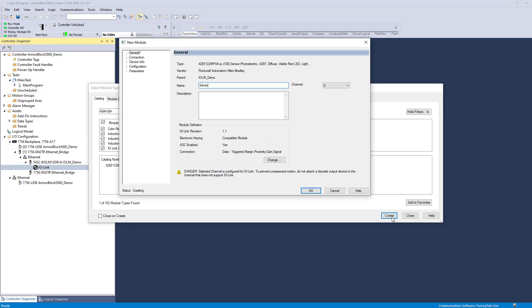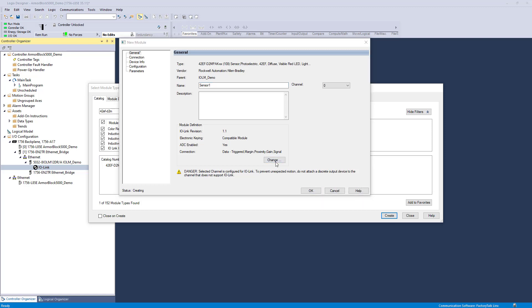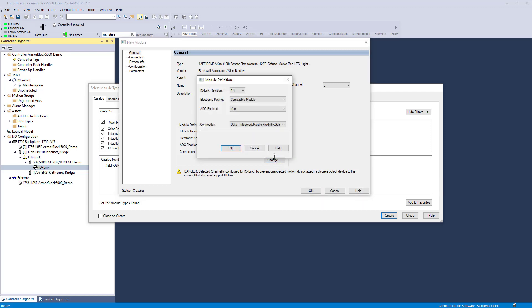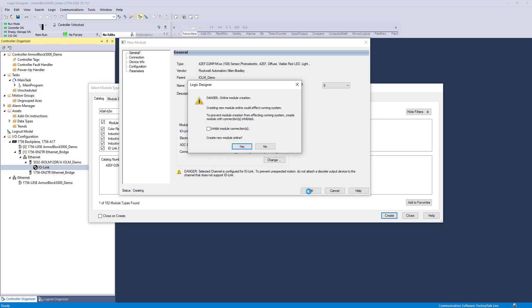When creating a device, you can edit the module definition and choose to use Automatic Device Configuration or ADC from the change window. Choosing No for ADC enabled will result in the device using Backup and Restore mode for data storage. Once the required configuration is entered, select OK. This process can be performed online.